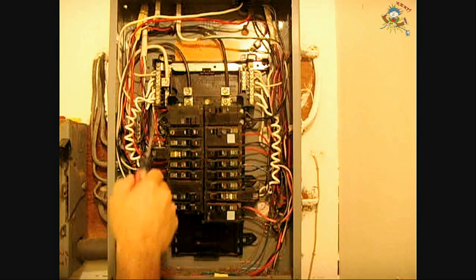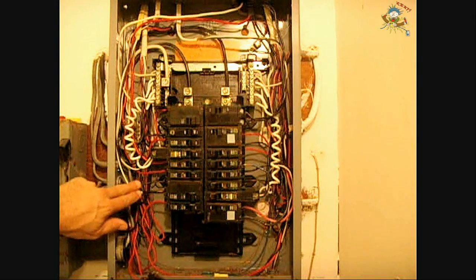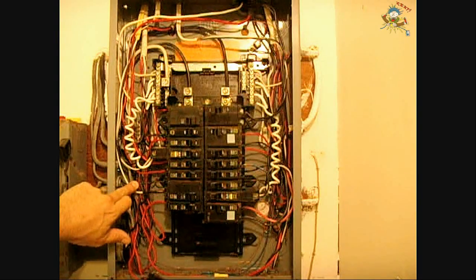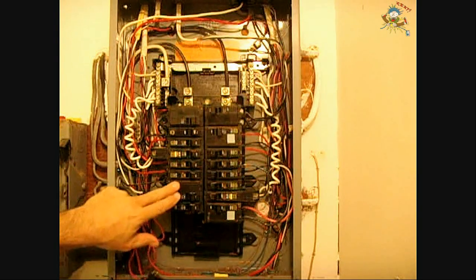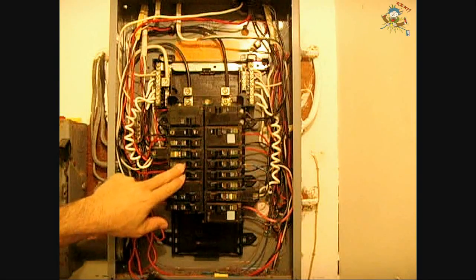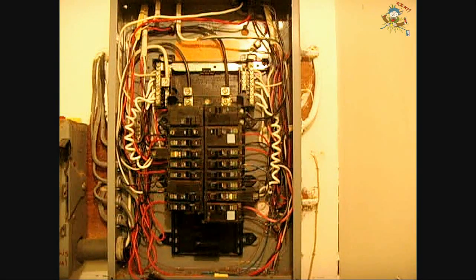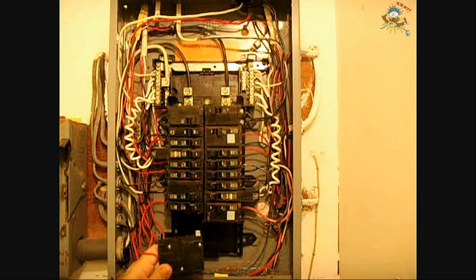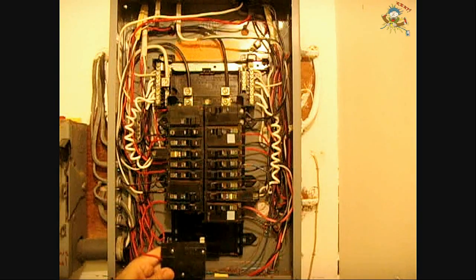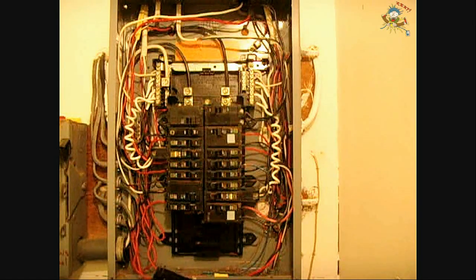Once you made sure all the screws are tight and you also made sure that all of these wires are the correct wires for the ampacity of each breaker, we can go on to another step. Now, a problem that's fairly common, especially in a lot of Challenger panels that were made back in the 80s and 90s, and there are some other companies as well. I would have people call me up for service calls, and I would get to their house and they'd say my hot water heater's not working, or my air conditioner's not working, and I would take a voltage reading.